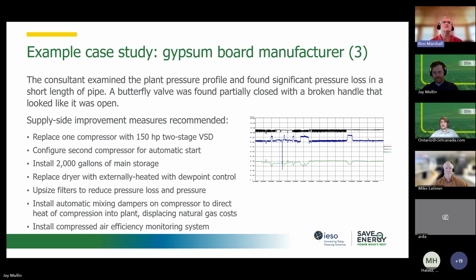Next slide. Yeah. Okay, so when we took a look at the pressure profile, we can see it there. The black line is the discharge of the compressor. The blue line is after the air dryers. The green line is somewhere out in the plant. Pretty significant pressure drop. So we found an issue with the butterfly valve that had a broken handle. The handle showed that the butterfly valve was open, but it was actually almost fully closed, right? So as we moved the pressure monitoring devices closer to that valve, we could understand that was a problem, right? So we looked at the KPIs and everything.